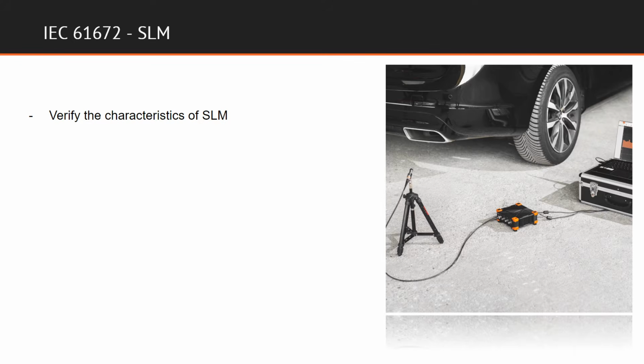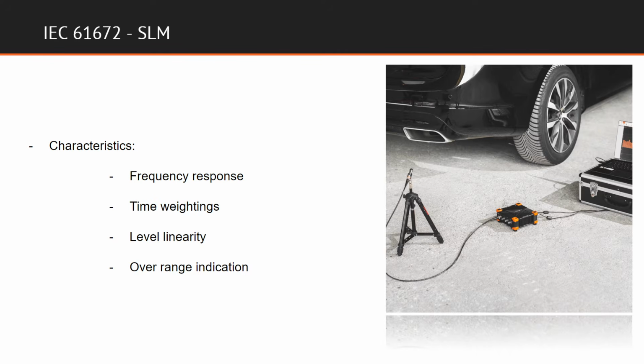Procedures for calibration include tolerances and are designed to verify that the characteristics of the sound level meter in question are indeed correct. Some examples of the test characteristics include frequency response of microphone and filter, the time weightings, for example, fast or slow, level linearity, overrange indication, and many other parameters.